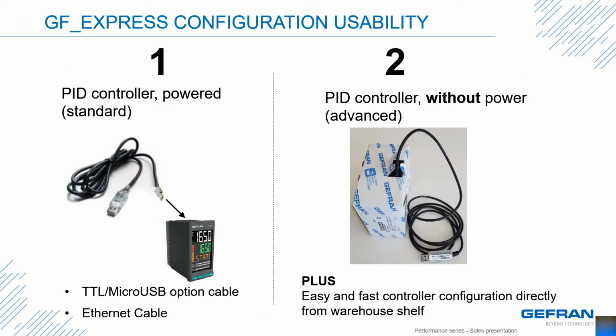GF_Express will work two different ways. First, if you power the instrument, you can use our TTL micro USB configuration cable. If the instrument has the Ethernet option installed, then you could just use a standard Ethernet cable. The second method, without power, is to use the TTL micro USB configuration cable. Power is supplied via the USB, and the instrument's microprocessor can be programmed. This means you could do it while it's in its box, or while you sit in your car or in a maintenance department without looking for power.